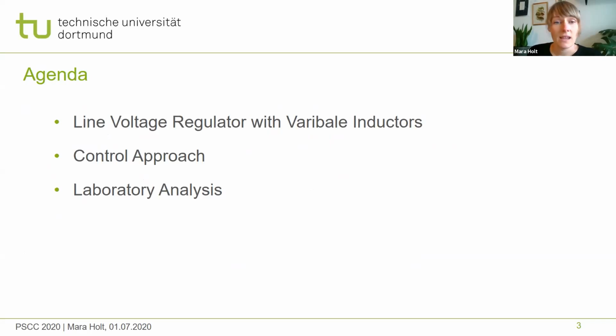The agenda of the presentation: first, we consider the working principle of the novel line voltage regulator, which uses variable inductors for continuous voltage regulation. Next, we deal with the control approach, which focuses on mitigating side effects like harmonic distortion emission and increased grid impedance. In addition, a model is developed to enable controlled system design. Finally, a laboratory analysis evaluates the novel line voltage regulator in comparison to a stepped one with regard to power quality.